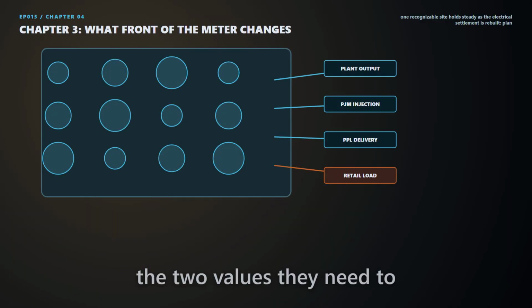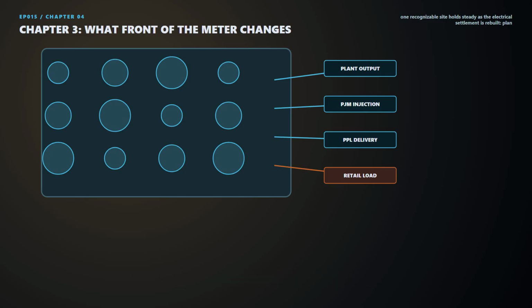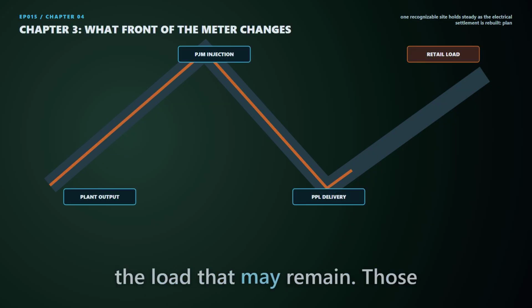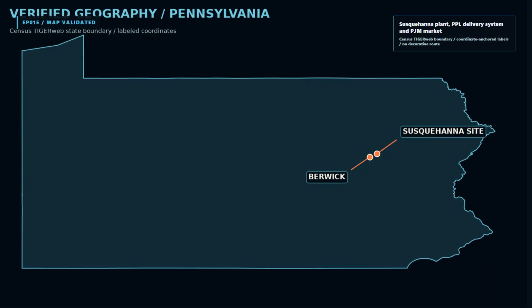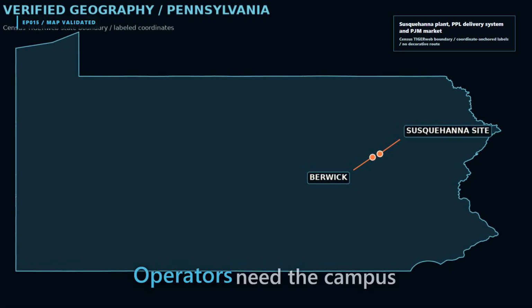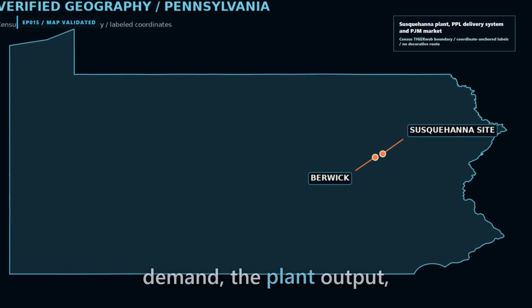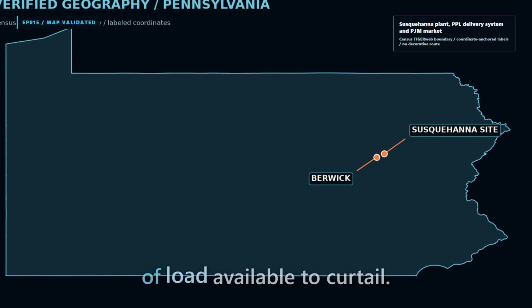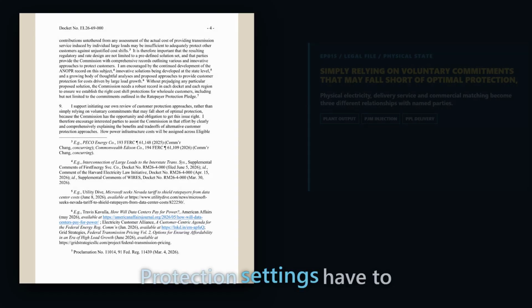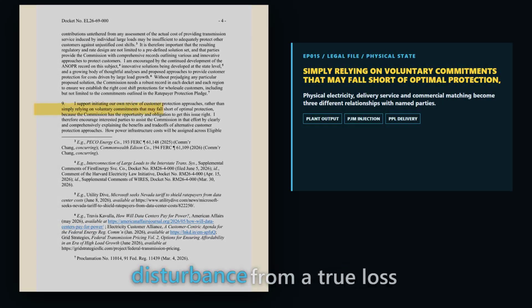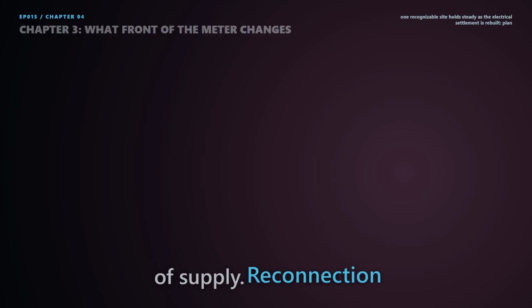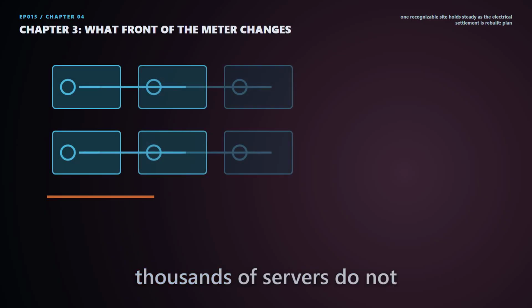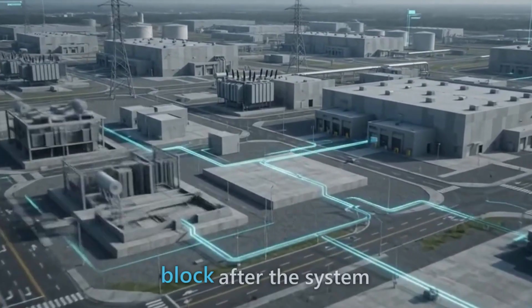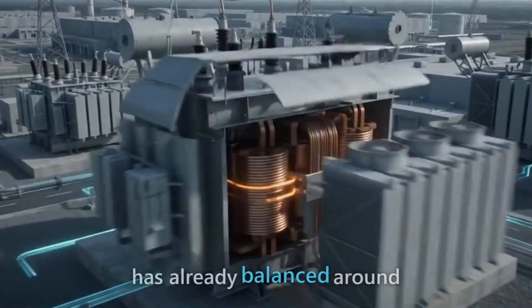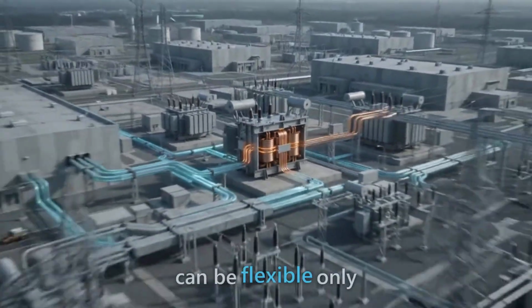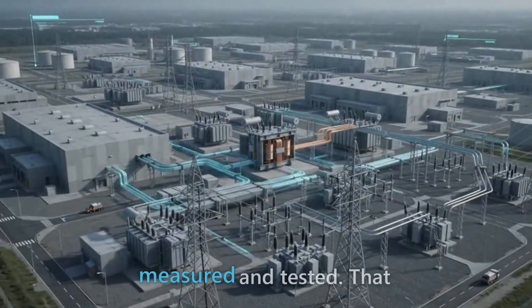It gives operators the two values they need to study it: the generator that can disappear and the load that may remain. Those values need real telemetry, not an annual estimate. Operators need the campus demand, the plant output, breaker status, and the amount of load available to curtail. Protection settings have to distinguish a short voltage disturbance from a true loss of supply. Reconnection must be controlled so thousands of servers do not return as one sudden block after the system has already balanced around their absence. A service can be flexible only when the flexibility is measured and tested.